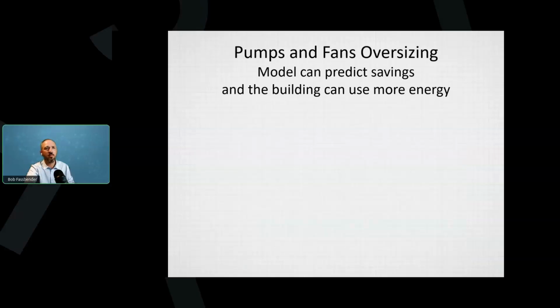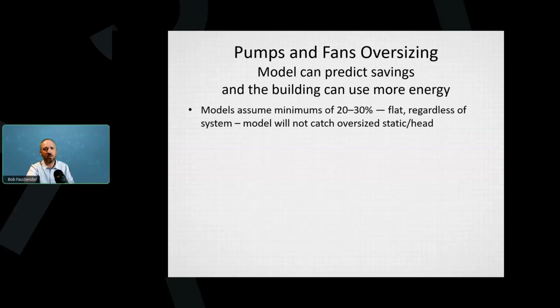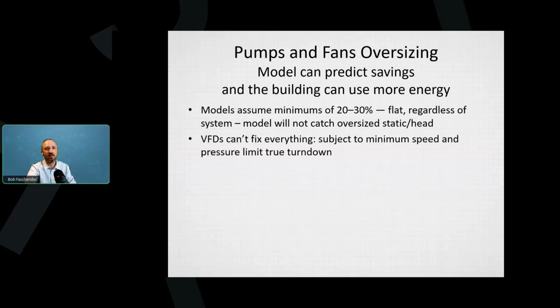Okay, so the model can predict savings, and the building can use more energy. And the reason why is the models automatically assume 20 to 30% no matter what you enter. It doesn't understand the pump head minimum charts for the most part. So when you actually size your pumps, the main thing that you want to check is that you're sizing it according to the modeled load, accounting diversity, things like that. The VFD cannot fix everything. It can only turn down the speed so much. And when we're looking at orders of magnitude of oversizing, you basically end up running a constant volume system.